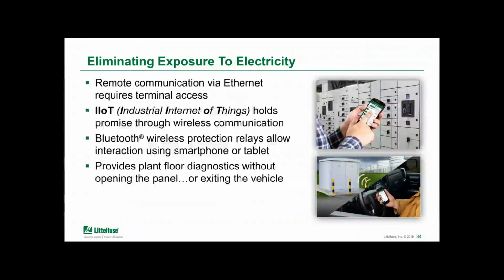So if we look at the hierarchy of controls pyramid, we've talked about varying levels of effectiveness that you can achieve by different design-in methods. But one of the most effective that we mentioned, and sometimes more difficult to achieve, is the elimination. Now, technology has advanced. So remote communications, such as Bluetooth, can be used to interact with these devices. And the net effect is that the worker can talk to these devices without even having to approach the panel.